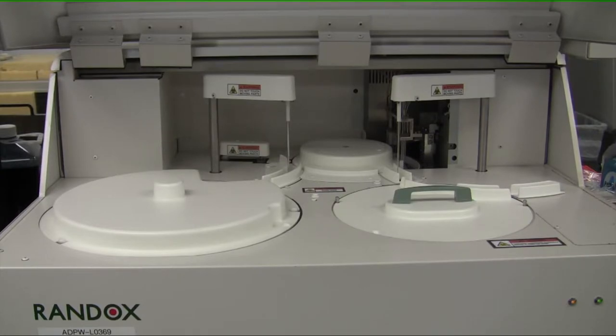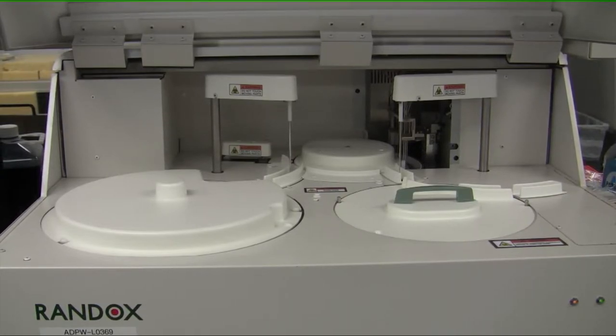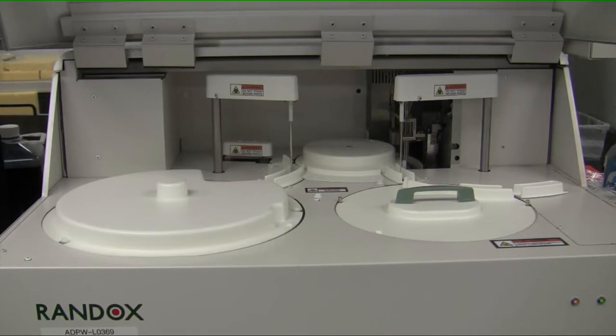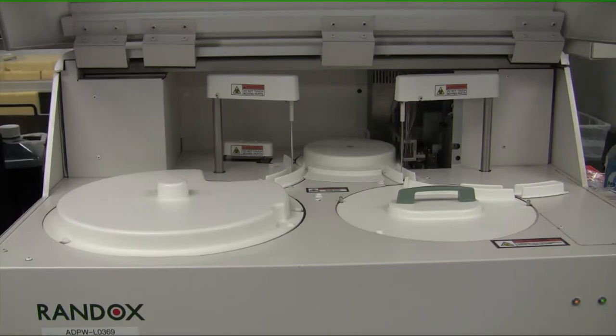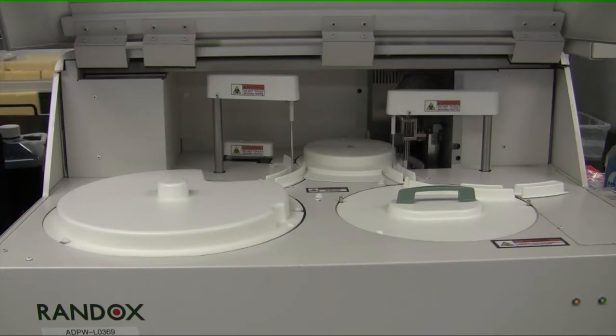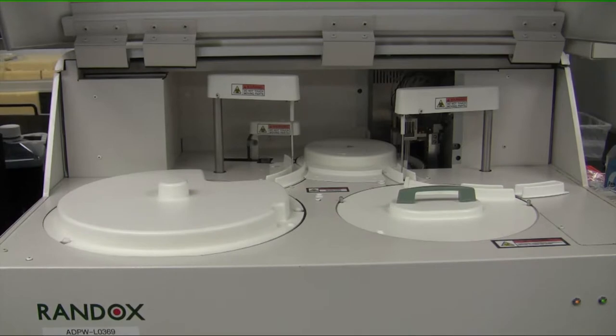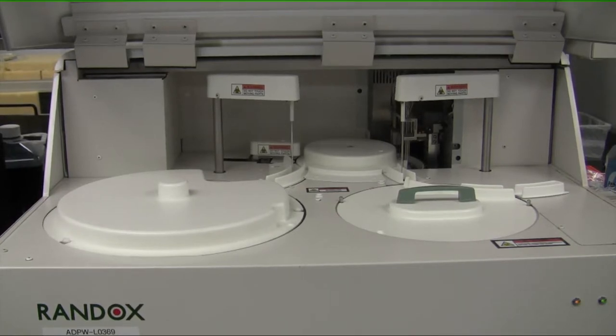And then those two materials, the sample and the reagent, create an enzymatic reaction, and then that creates a color. The color is then measured and correlated very accurately to a metabolite concentration. There you see in the back, the mixing arm is springing into action, doing some mixing, and going back to its wash position.